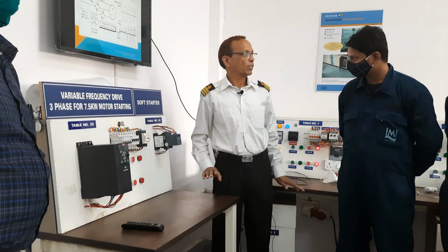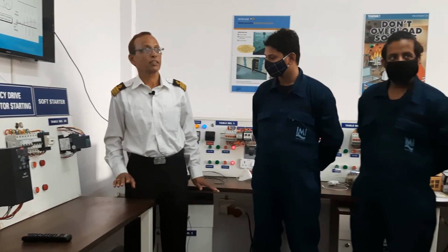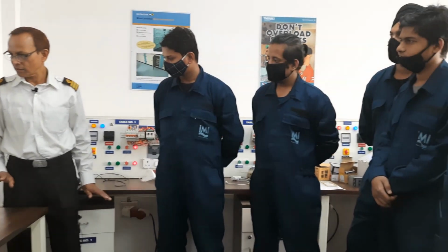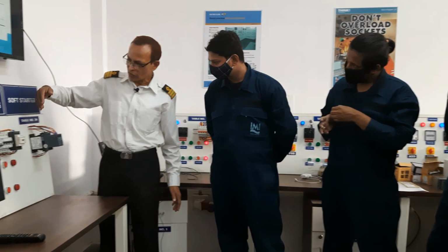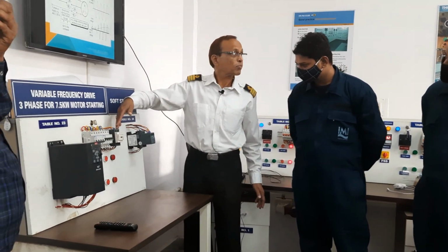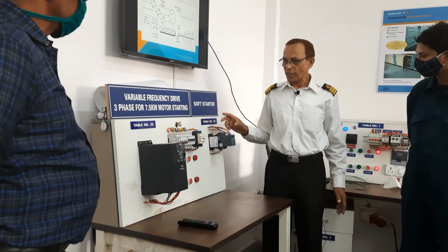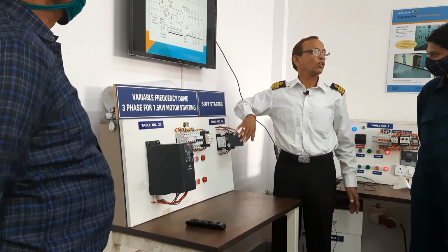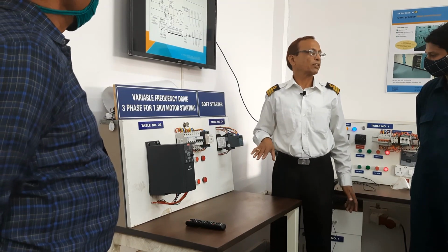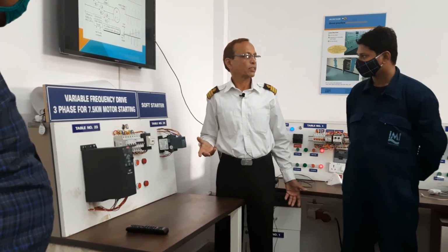Okay. Hope it is clear to all. Any doubt? Like, we could have connected this to the contactor and taken power from here. So when it is cutting off, after the timer changes over, the motor will run directly with this contactor. This is bypass. So the burning of this will not take place. Right?